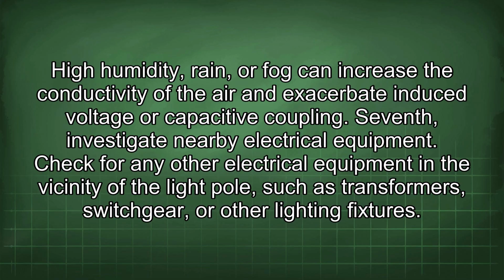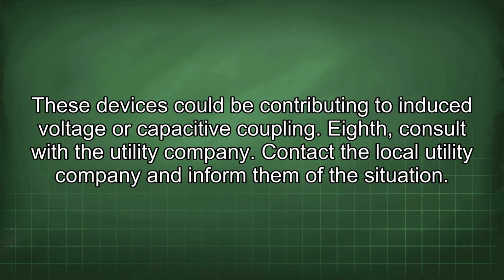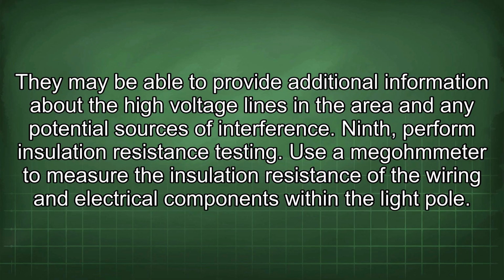Seventh, investigate nearby electrical equipment. Check for any other electrical equipment in the vicinity of the light pole, such as transformers, switchgear, or other lighting fixtures. These devices could be contributing to induced voltage or capacitive coupling. Eighth, consult with the utility company. Contact the local utility company and inform them of the situation. They may be able to provide additional information about the high voltage lines in the area and any potential sources of interference. Ninth, perform insulation resistance testing. Use a megohmmeter to measure the insulation resistance of the wiring and electrical components within the light pole.